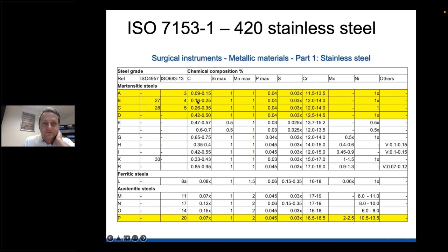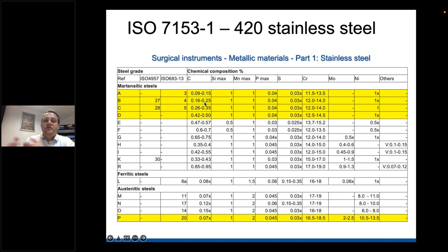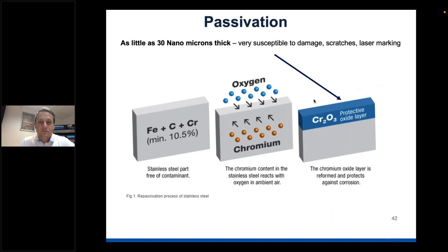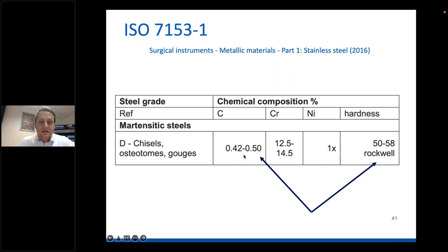Carbon content is key: the higher the carbon, the higher the hardness achievable. A steel with 0.42% carbon would be for something like an osteotome or chisel - very hard. A lower carbon steel, when hardened, still has flexibility, which is offset by higher chromium content. The osteotome requires higher carbon to achieve hardness - if you're manufacturing something like an osteotome, chisel, or gouge that has a cutting edge, it must have that level of hardness, otherwise it would dent continuously after use and would not be fit for purpose.